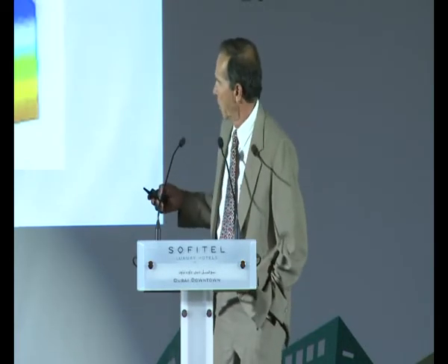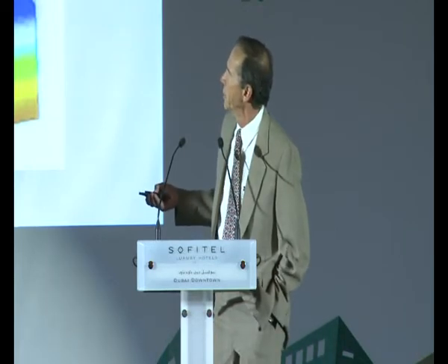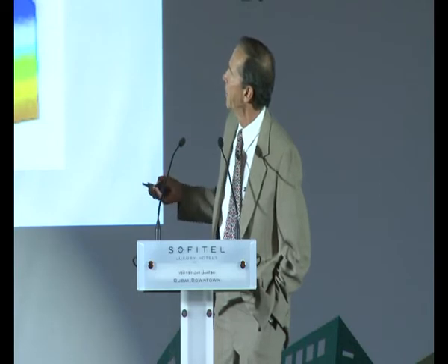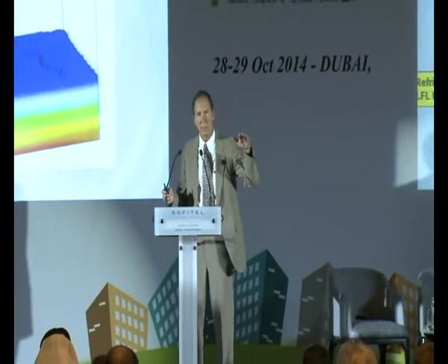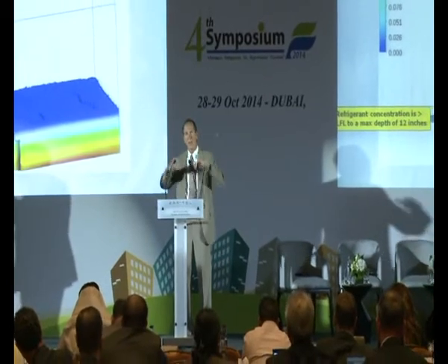Here's what the physics looks like. This is an actual run. This is a picture of the output of the run. What you can see is, as the refrigerant is released, much as you've heard before, the refrigerant is denser than air. It falls to the floor. And you can see that the refrigerant concentration at the LFL, 14%, rises to about 12 inches, about a half a meter. So the refrigerant releases, it hugs the floor. The LFL, below about a half a meter, is capable of being ignited, and then full dispersion occurs.